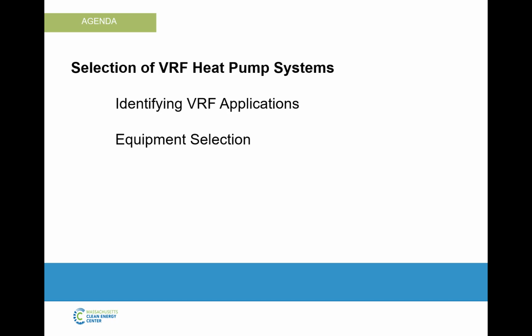And one of the biggest factors that's going to influence the VRF system cost is zoning. If we take just this space, I could put a VRF system in here with one fan coil unit, and that's a very cheap installed cost. Or I could divide this room up into 20 different zones with 20 individual offices, 20 different fan coils and 20 different thermostats, and you have a significantly different cost value there.